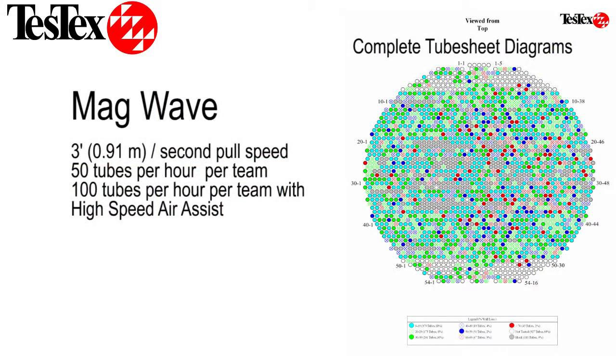The average pull speed of MagWave is approximately 3 feet per second. MagWave has been used with our high speed air assist to increase productivity. We can collect data from 50 to 100 tubes per hour, per two-man team.